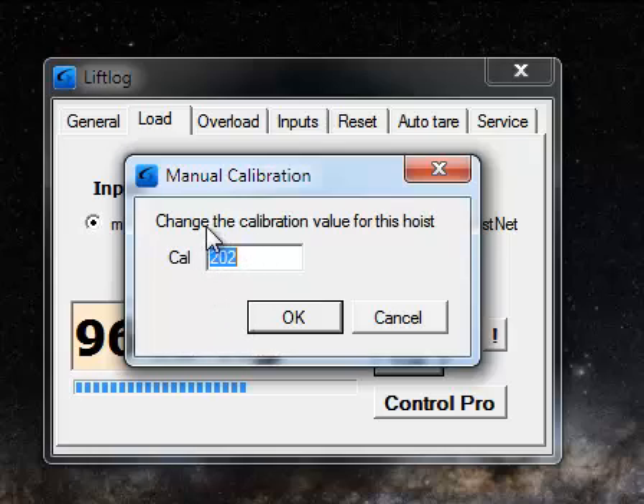And this shows me the calibration value for this device. And again, this works on Liftlog, Traffic Lite, MaxOut, HiBeam, and LiftlogXL, and all the products that sense load. Now in this case, this calibration value is 212. That's a good calibration. If your calibration value is below 100, then you're going to start to see problems. And if it's below about 50, then it's probably a reasonably poor calibration. What you should do in those cases is look at the manual, watch the video on commissioning on Liftlog, and increase the gain in the system.